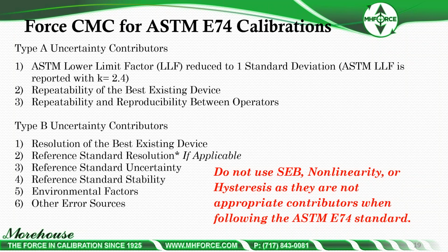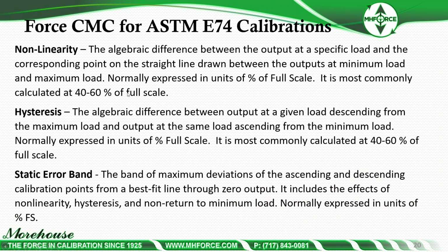I'm saying on this one, do not use SEB, nonlinearity, or hysteresis, as they are not appropriate contributors when following the ASTM E74 standard. You're calibrating to a known standard, and they're just not applicable.